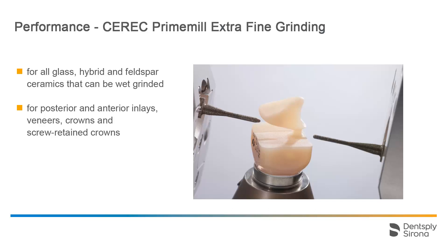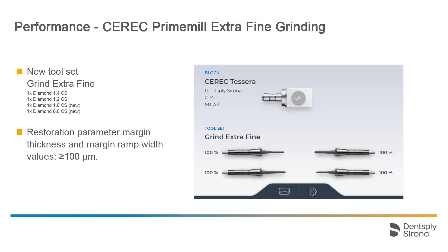For all glass, hybrid, and feldspar ceramics that can be wet-grinded, the Primemill Extra Fine Grinding mode can be selected. This applies to crowns, inlays, veneers, and screw-retained crowns both in the posterior and anterior region.